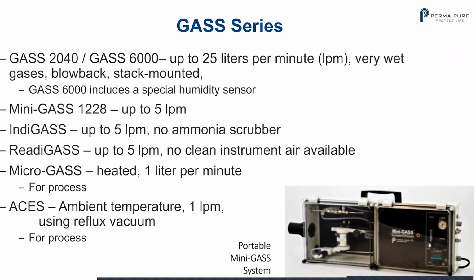The ReadiGASS is a newer product, also up to 5 liters per minute, but that's designed for emerging markets where no clean instrument air is available. We actually have a system to provide and make its own purge gas, and we're able to use dirty air that isn't very dry in order to make that reliable. We also have the Micro-GASS, which is also heated for 1 liter per minute flow rates. That's mostly for process. And we also have the ACES, which is a version made for ambient temperature applications, also up to 1 liter per minute using reflux vacuum, also for process.